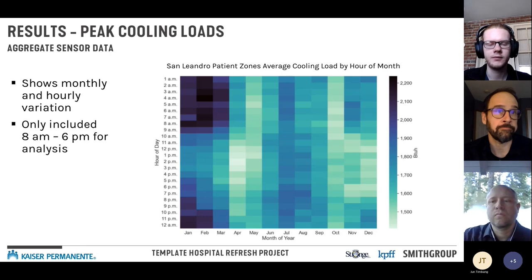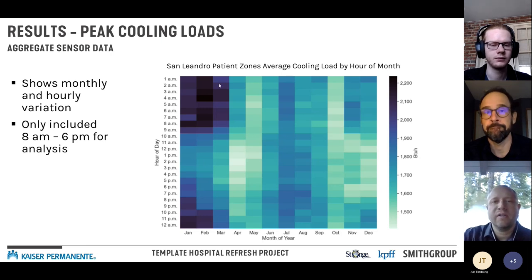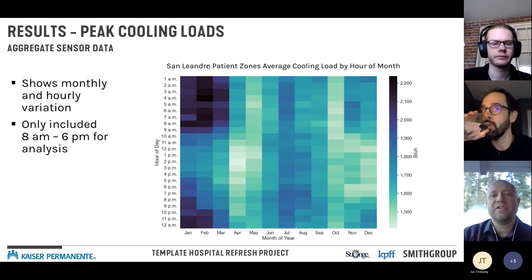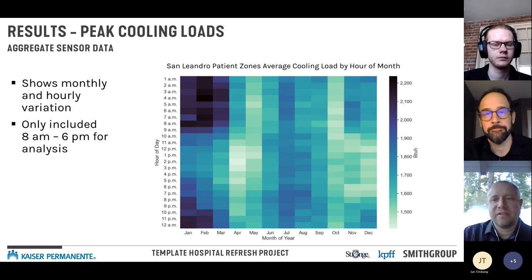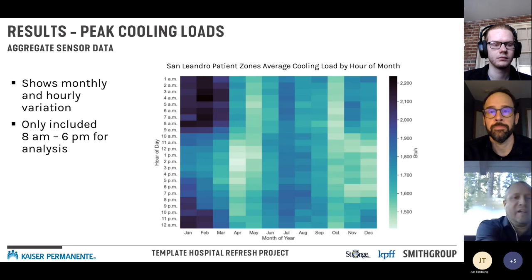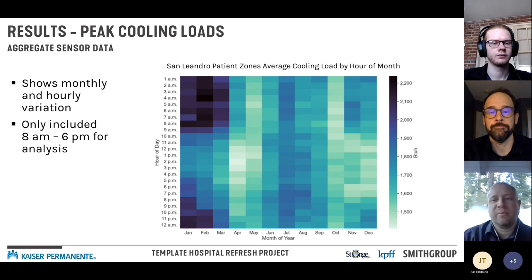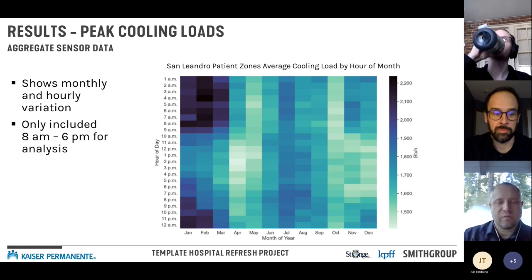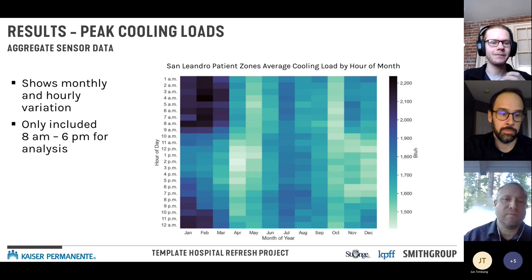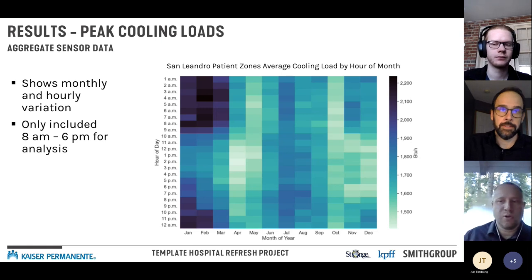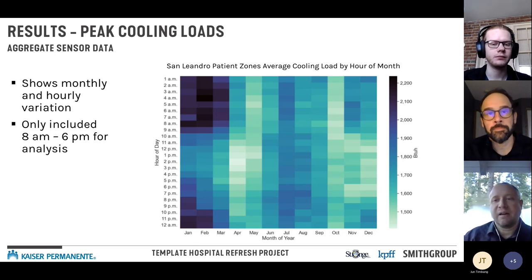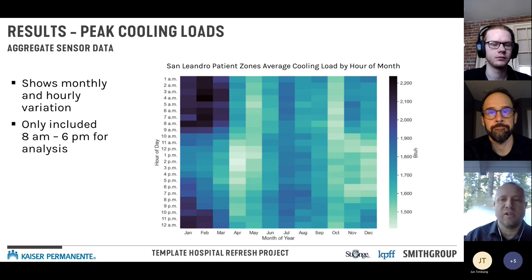When we dove into individual zones, a perimeter zone in San Leandro showed its annual peak cooling at 1 a.m. in January — unexpected. Looking at the five-minute raw data, we found rapid over-reheat: the reheat was hunting for the room set point, way overheating the space, and then the cooling had to compensate. We didn't think that was representative of actual cooling performance, and because it was isolated to a number of units, that's what drove the filtering Peter mentioned.